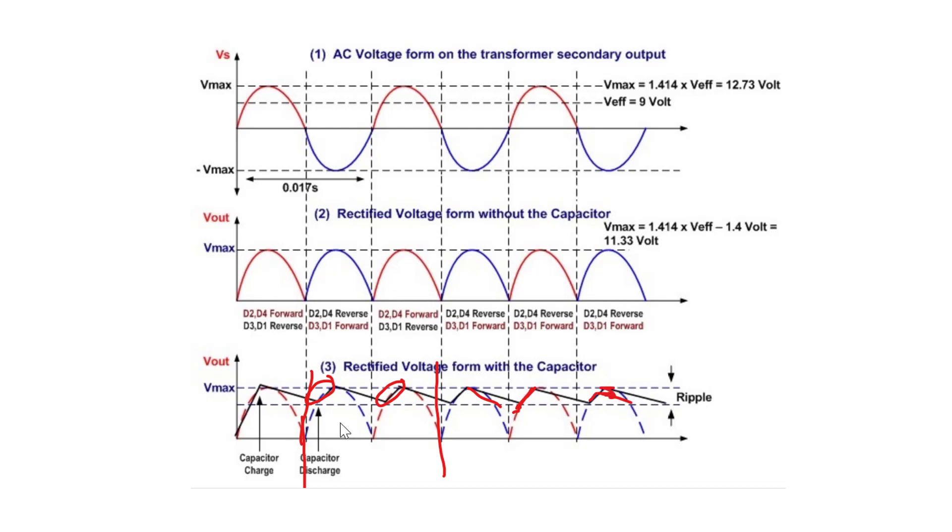So my drawing here might be shite. But anyway, I just wanted to kind of show you guys that. I don't know how much duty that is out of each sine wave, but it's got to be a lot less than this. Of course, you get peak amplitude at the peaks every time. However, you still got current increasing from zero up to peak and then back to zero along the way of those peaks. It reads correctly with the meter on a motor, but it isn't reading correctly feeding into the rectifiers into the bank of capacitors.